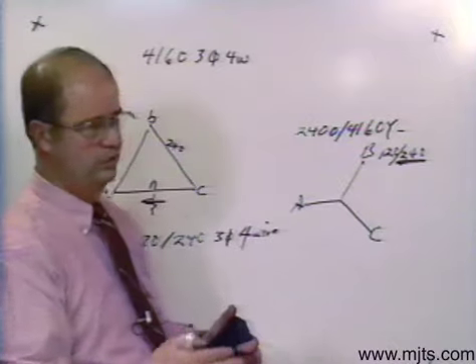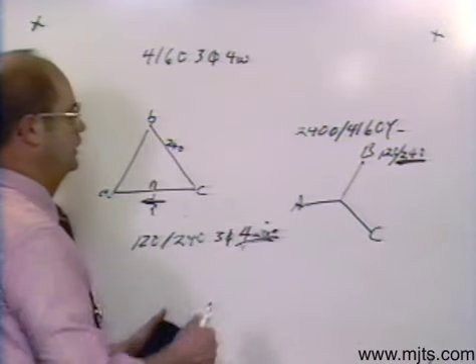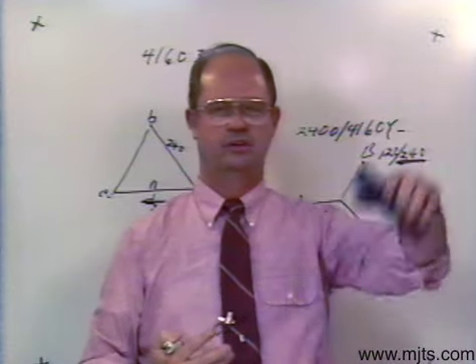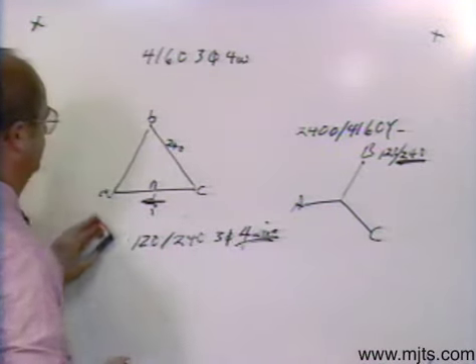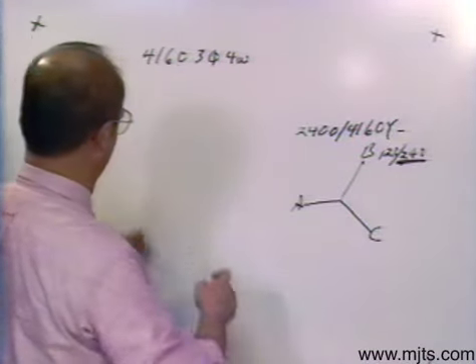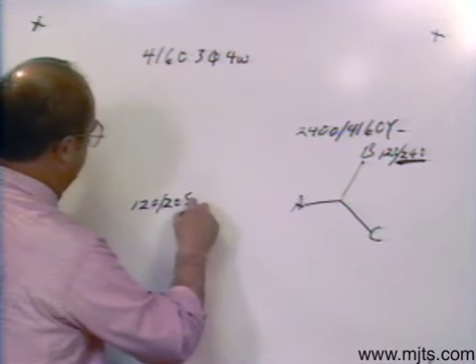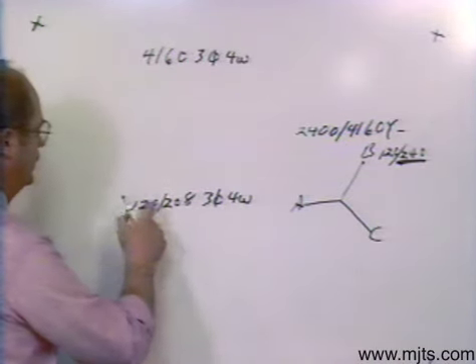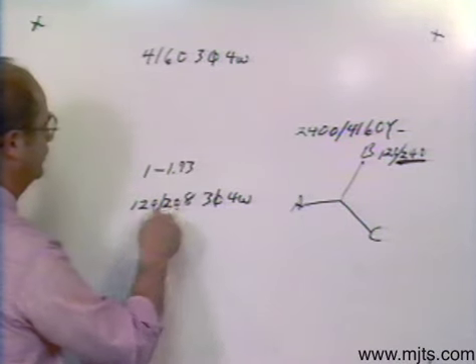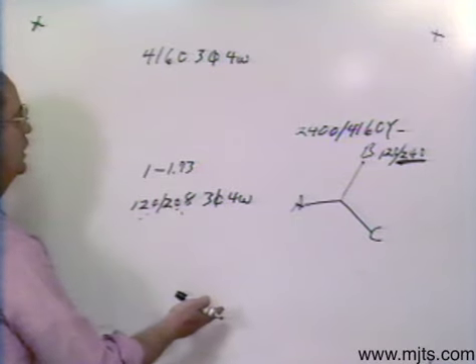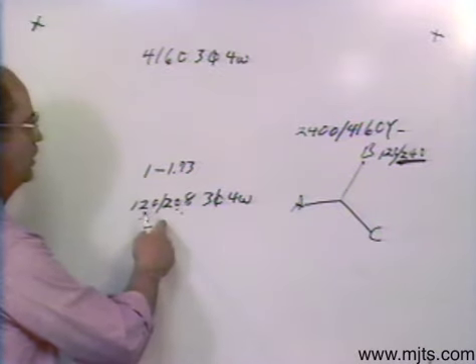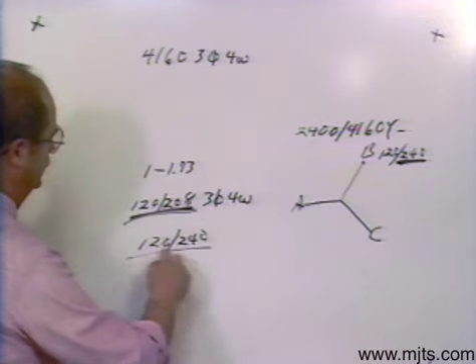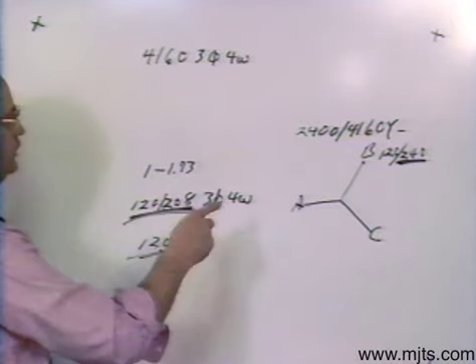When you get down to the consumer's level — voltage below 2400 volts — don't go by the number of wires as to whether it's a Y or delta connection. You can't do that. We can only do that on our distribution systems, sub-transmission, and on up into higher voltages. Now if we have a Y system — say my rating is 120/208 for the low side, 3-phase, 4-wire — the reason it's Y is because I've got a 1-to-1.73 relationship in those two numbers. Go by those numbers as to whether it's a Y or a delta connection on the low side.